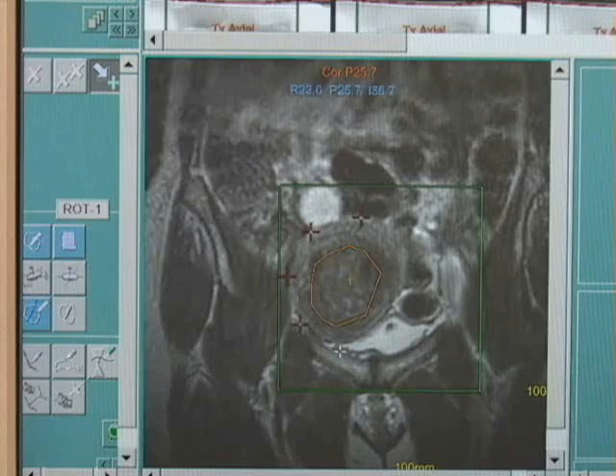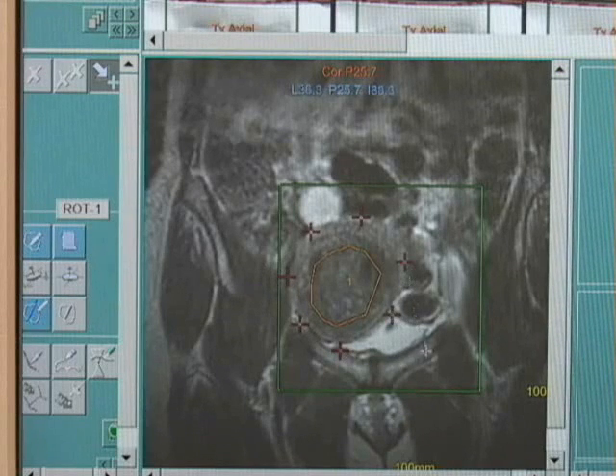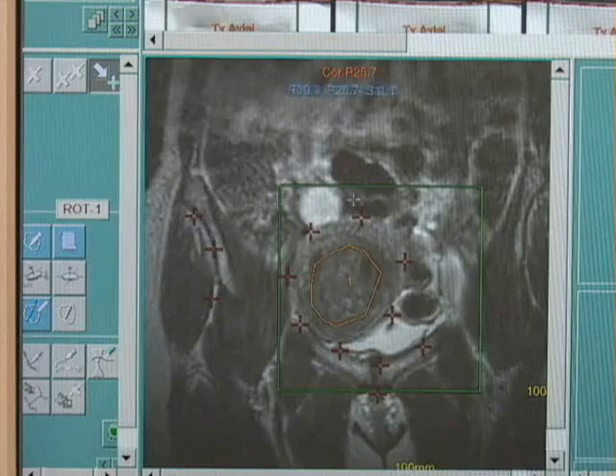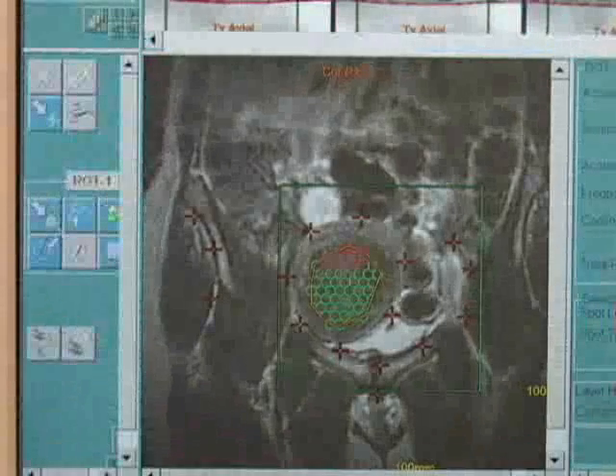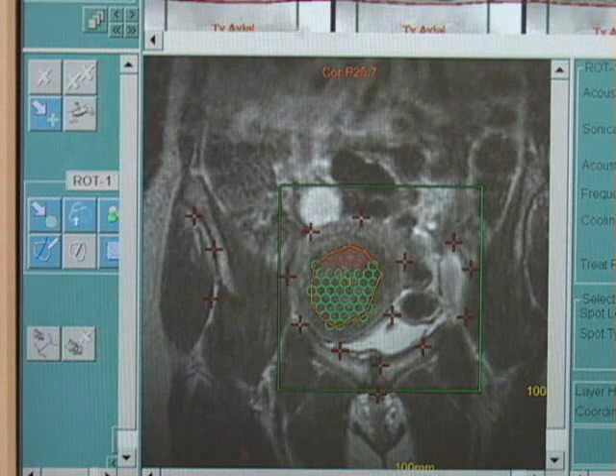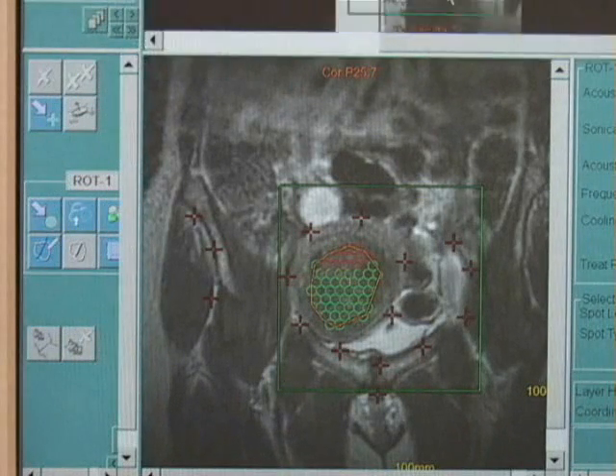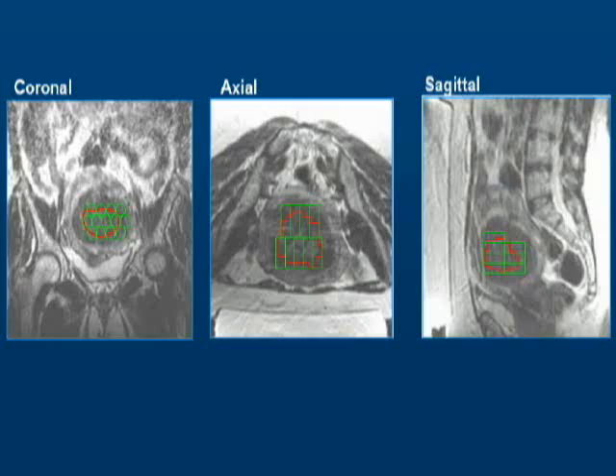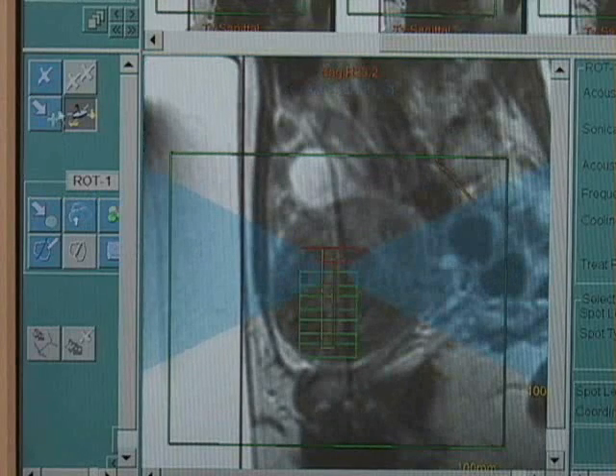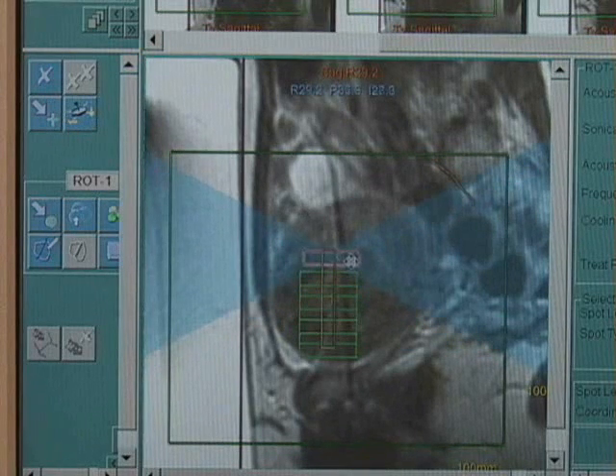Fiducial markers are added as an additional safety measure. Major points of anatomic reference are marked to help identify patient movement. Based on the tumor volume and depth of the prescribed treatment volume, the system computes the energy, number, and size of spots appropriate for the treatment. The spot is cylindrical in shape and can vary from a few millimeters to 10 millimeters in diameter and 45 millimeters high. The sonication spots are colored to provide additional safety feedback.